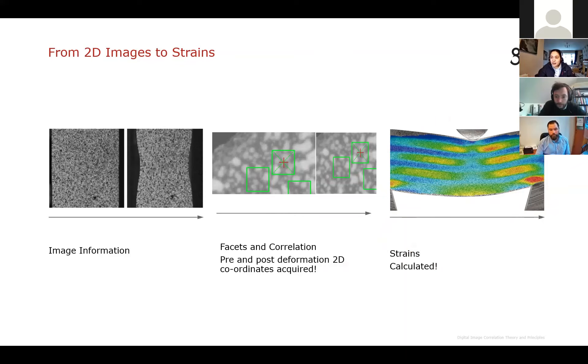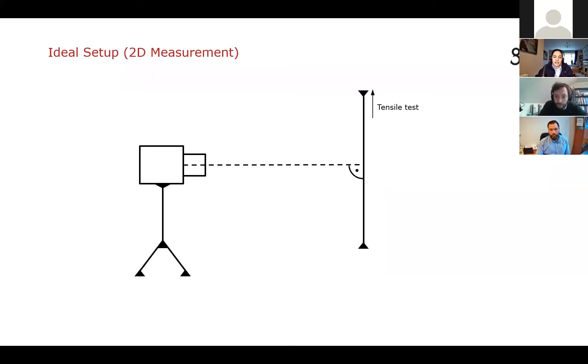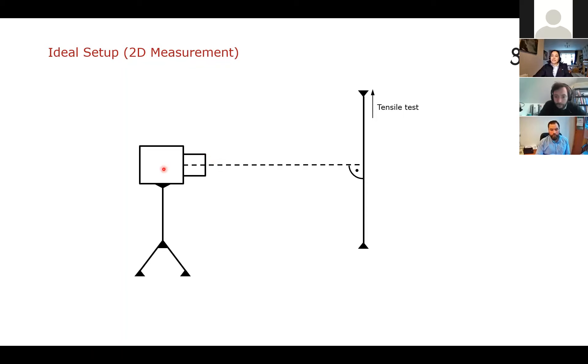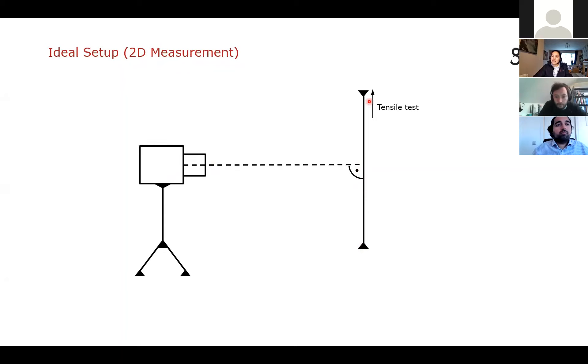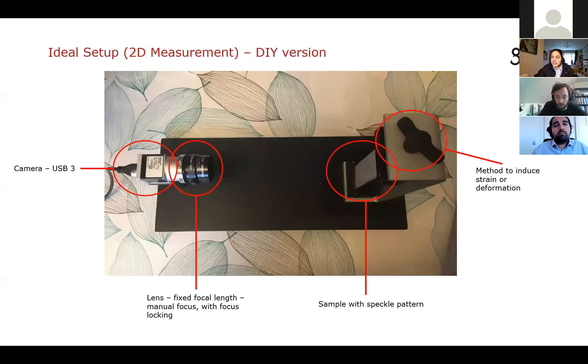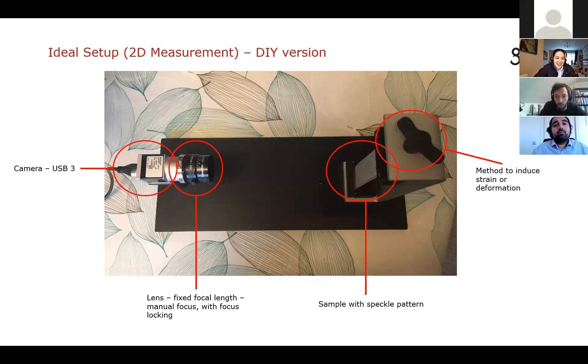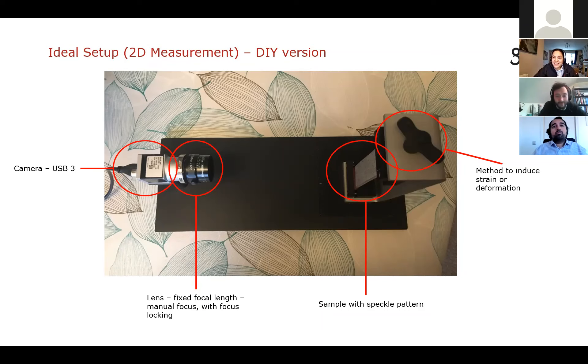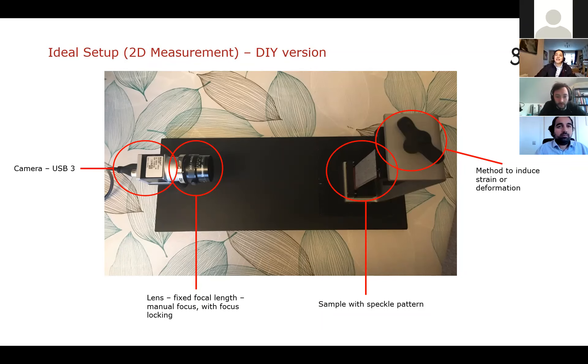So what does an ideal setup look like? Ideally, you've got a camera with a lens and it's looking at a sample. So for a 2D measurement, this camera needs to be perfectly perpendicular to our sample. Our sample needs to be flat and the deformation of the sample needs to be in the direction perpendicular to the camera. So what does this sort of setup look like? This is the setup I have at home. Yeah, I do DIC in my living room every time I do a training course. We do a very quick DIC measurement. So in this example, I've got a USB 3D camera. Sorry, it's very much a 2D system.